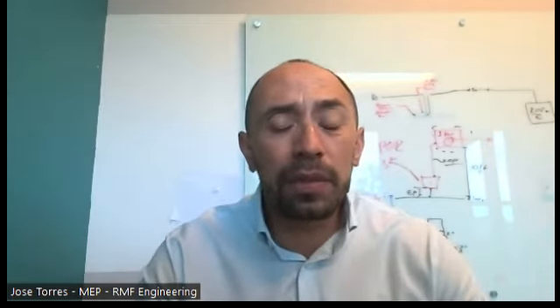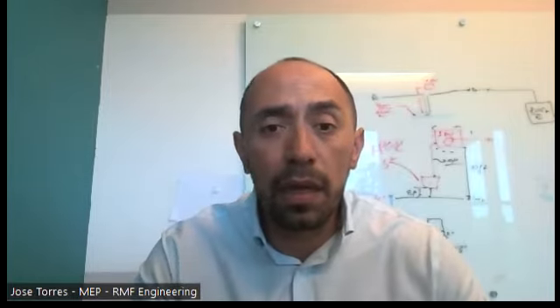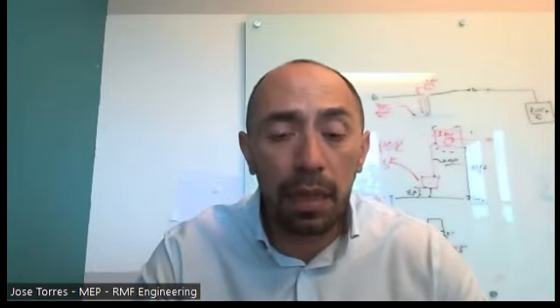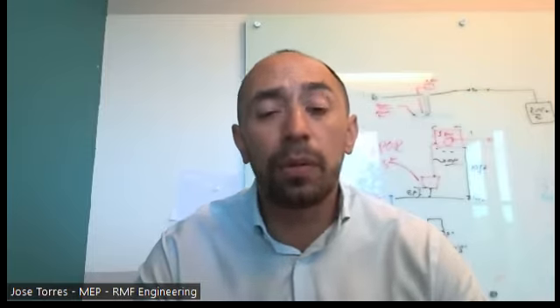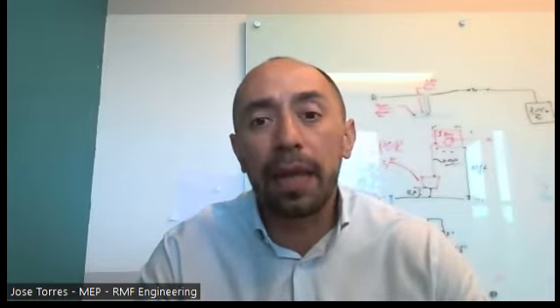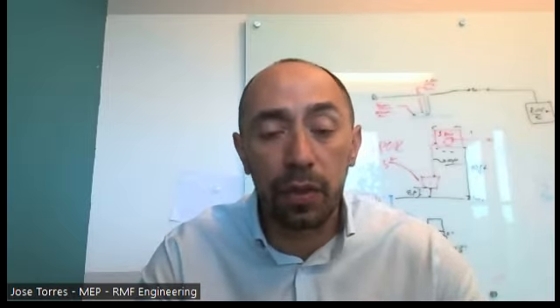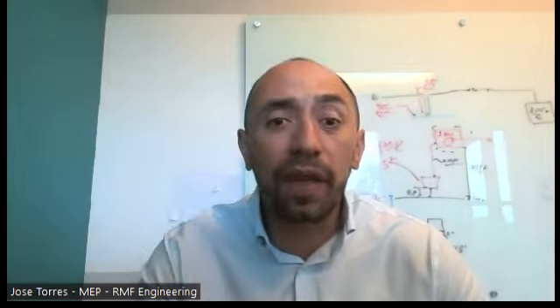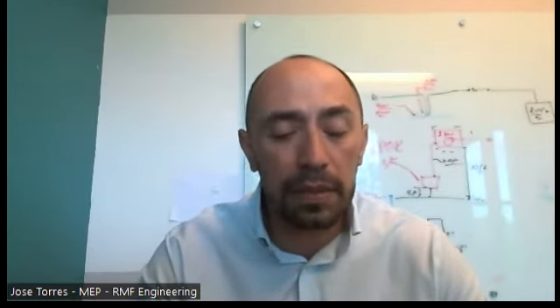Did you have an opportunity to look at the existing conditions of this equipment, of the system? Did you have an opportunity to review code? When was the existing system for the facility designed? How many times has it been repaired? What are the headaches with it? What do your staff enjoy working on it? What are things that are no longer available? Those are some of the questions we typically start asking when we get invited to replace an air handling unit, a chiller system, domestic water system, oxygen tank farm, generators. It's the questions we start with, because in general, we need to define the true scope of the work.